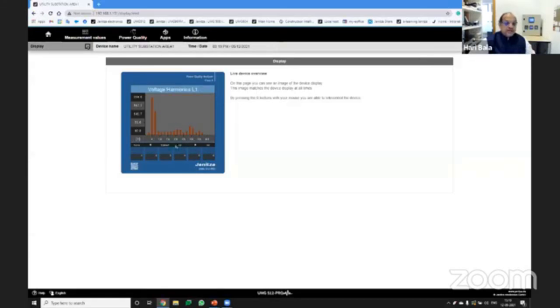And then you can have the voltage harmonics as absolute values. And then if I wanted to see the other parameters for the other phases, or if I wanted to see the current, or I can see the different currents. The next way is seeing the voltage line writer or a current. This is how my currents are going on over here. And then you can also have the transients. Whenever it is occurring, you would be in a position to see those values entered. You could see a transient on the voltage and current over here. That's a possibility. And then you could see events. You could see the phasor diagram, which is very important for any commissioning engineer to see how things are happening during the commissioning stage. And then you can see a waveform as well, how the current and voltage waveform is behaving. Yeah, so this comes up accordingly and also according to flicker.